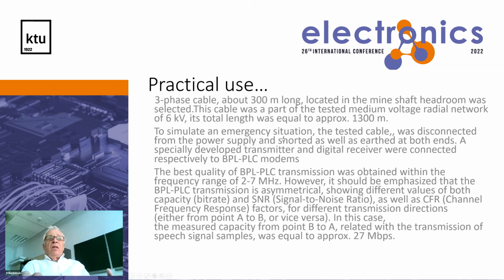And to simulate the emergency situation, the tested cable was disconnected from the power supply, shorted on both sides, and earthed at both sides. The best quality of transmission was obtained within the frequency range between 2 and 7 megahertz. However, it should be emphasized that BPL transmission, no matter whether it is voice or any other signal, is asymmetrical.